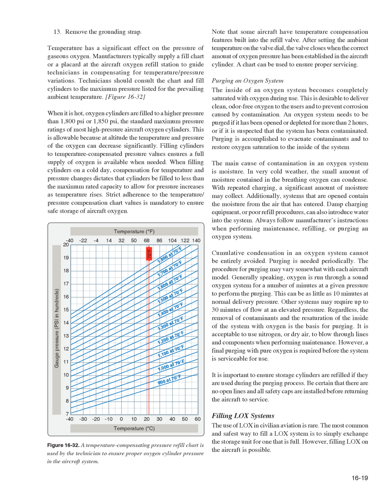Purging an oxygen system. The inside of an oxygen system becomes completely saturated with oxygen during use. This is desirable to deliver clean, odor-free oxygen to the users and to prevent corrosion caused by contamination. An oxygen system needs to be purged if it has been opened or depleted for more than 2 hours, or if it is suspected that the system has been contaminated. Purging is accomplished to evacuate contaminants and to restore oxygen saturation to the inside of the system.